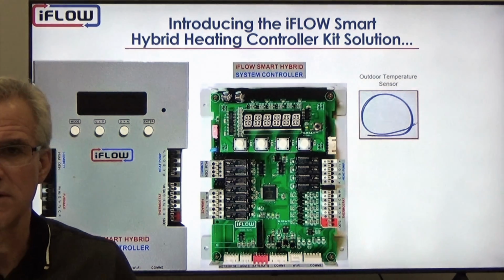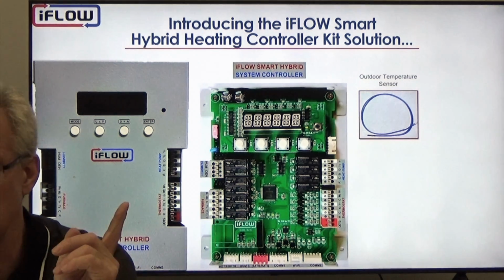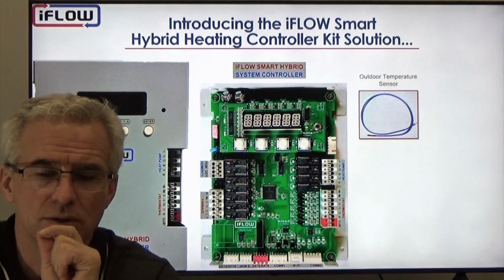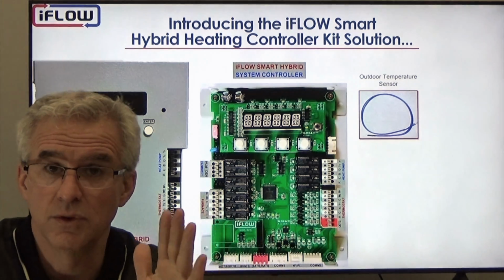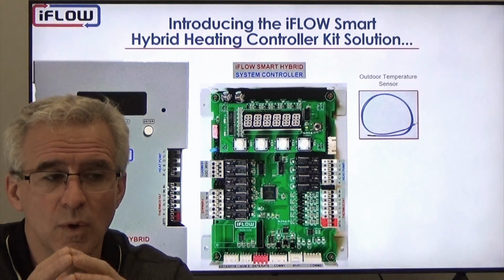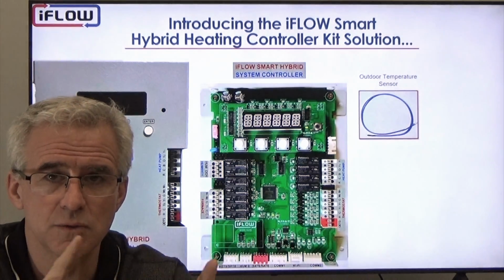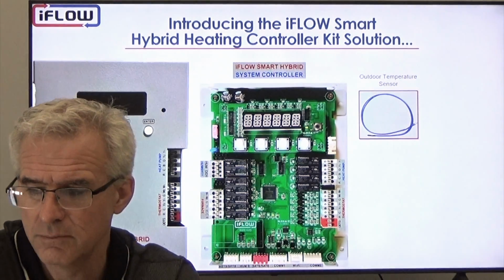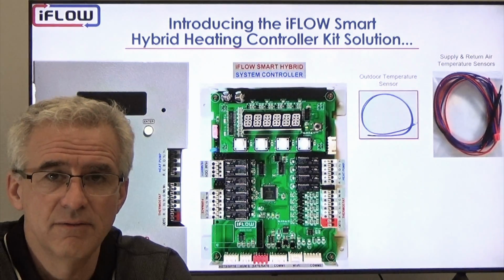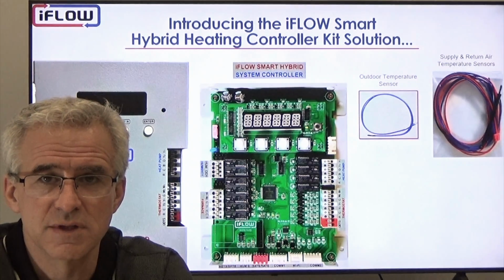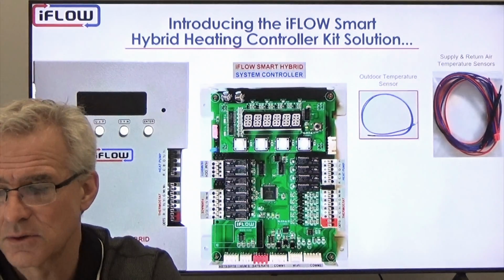The additional sensors: we have an outdoor temperature sensor. We need the outdoor temperature sensor to allow the iFLOW to know what the outdoor temperature is, so we can switch based on outdoor temperature. We also have a supply and return air temperature sensor, so we'll install that into the ductwork.